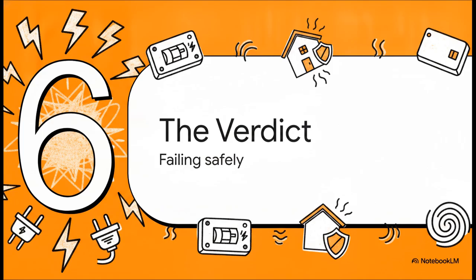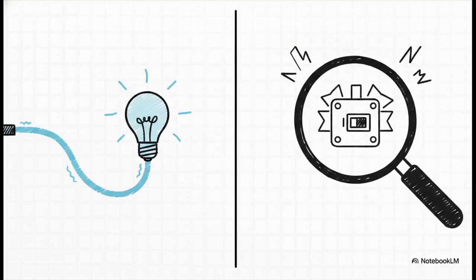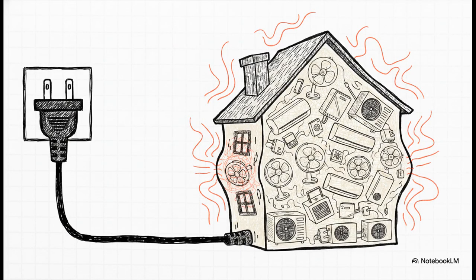Section 6, the verdict. Failing safely by design. Here is your biggest takeaway for today. A healthy circuit carries its intended load, period. A new pattern of tripping is evidence to investigate. While summer heat absolutely reduces your margin of safety, you should never dismiss a new pattern of tripping as just normal summer behavior. If it starts happening without any obvious added appliances, it is always evidence that needs to be taken seriously. The hot night doesn't magically make the electricity flowing into your home stronger. It just drastically increases the demand on your home while simultaneously squeezing that thermal safety net we talked about earlier.